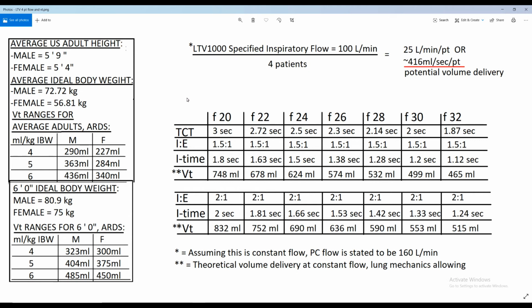So it would be pressure control, it would be AC, there'd be no spontaneous efforts because we already said that would wreak havoc on the system, so our patients are already paralyzed, so the machine is doing all the breathing. If we set the rates that we're typically going to see with patients like this, somewhere in the 20s to low 30s, we shouldn't really be going higher than that because these are adults at the end of the day. We've got our cycle times decreasing ever so slightly as the rate increases. We're going to keep our I to E ratio the same for this top set of data, and then the I to E ratio switches for this bottom set of data right here.